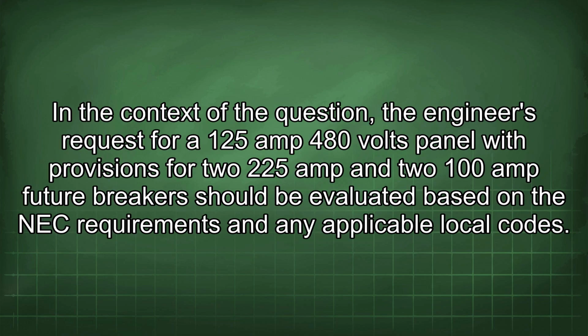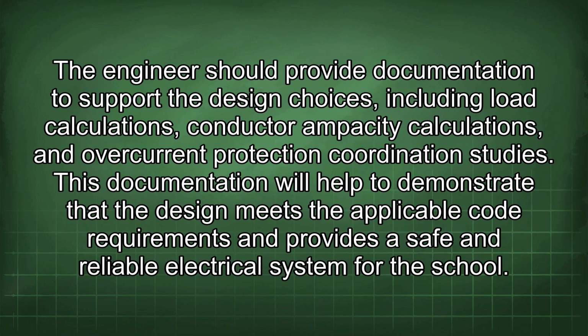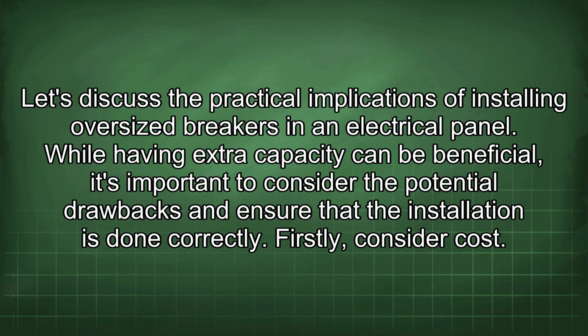In the context of the question, the engineer's request for a 125 amp 480 volt panel with provisions for two 225 amp and two 100 amp future breakers should be evaluated based on the NEC requirements and any applicable local codes. The engineer should provide documentation to support the design choices, including load calculations, conductor ampacity calculations, and overcurrent protection coordination studies. This documentation will help to demonstrate that the design meets the applicable code requirements and provides a safe and reliable electrical system for the school. Let's discuss the practical implications of installing oversized breakers in an electrical panel.